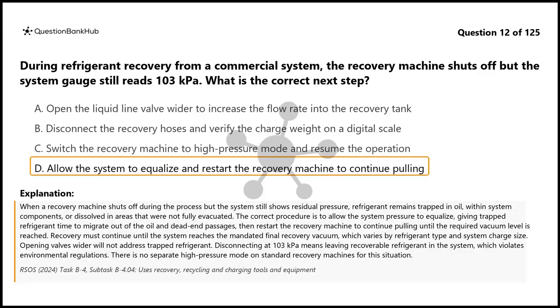Recovery must continue until the system reaches the mandated final recovery vacuum, which varies by refrigerant type and system charge size. Opening valves wider will not address trapped refrigerant. Disconnecting at 103 kilopascals means leaving recoverable refrigerant in the system, which violates environmental regulations. There is no separate high-pressure mode on standard recovery machines for this situation.